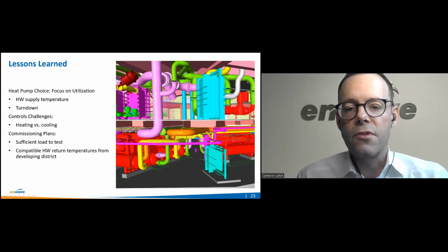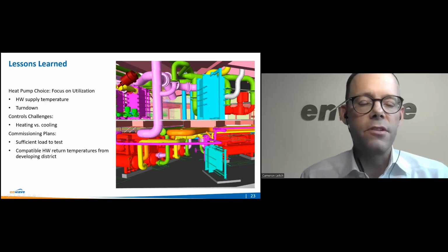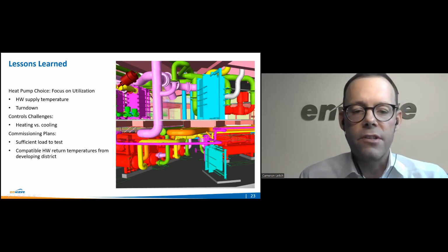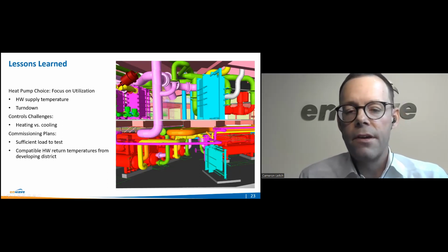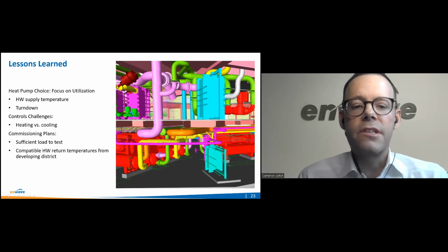Secondly, the high-lift centrifugal chillers at DHR Plant 1 have limited turndown. And so at especially low loads, there may not be adequate district heating load to operate these units. It was important to have higher turndown capabilities at DHR Plant 3 to extend their operating range.